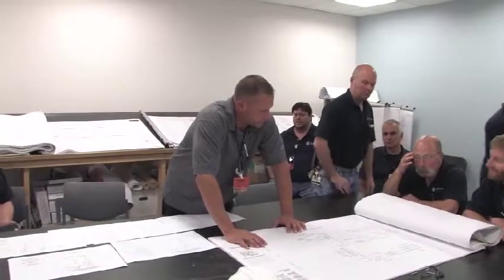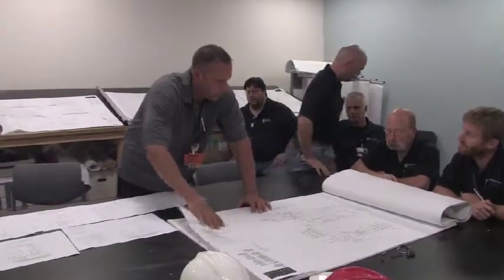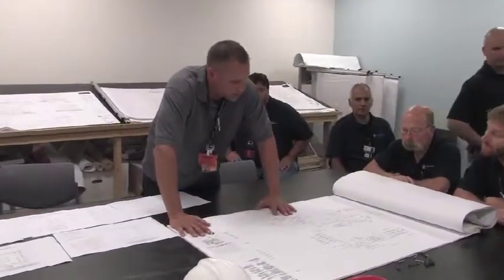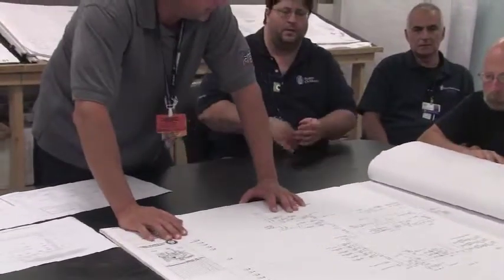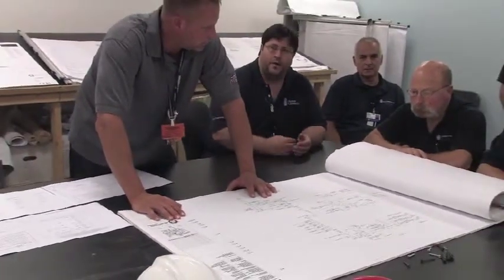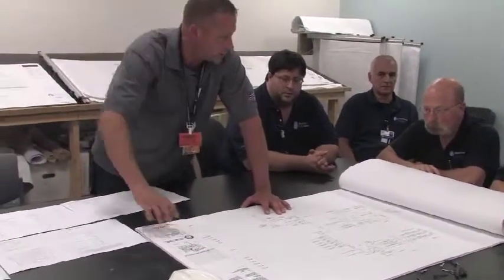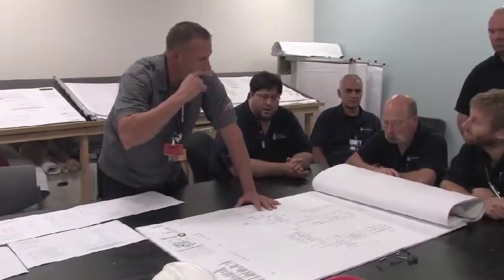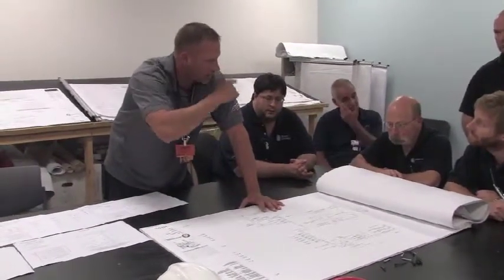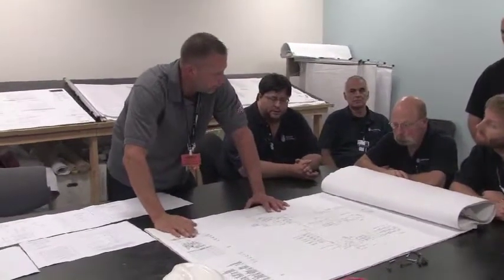There's two systems. We have 3 heat exchangers in the penthouse that do the hot water for the VAV boxes, reheat coils, and fan coil units. Then on the 4th floor, there's another heat exchanger that does strictly the glycol. The only place there's glycol in the building is for the overhang radiation on Binney Street and the ambulance ramp. In the 4th floor mechanic room, it's actually the underside of 5 against the existing building. There's a radiation loop out back there.